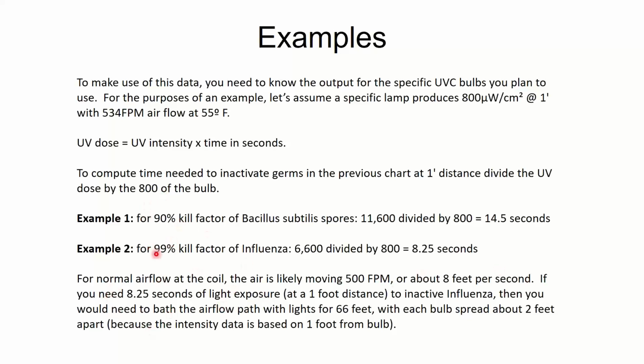I was already starting to jump onto the influenza one. Sorry, that was the bacteria one, 14 and a half seconds. Influenza, to kill 99% of the flu, I need 8.25 seconds. That's the one I was describing here. So to get that kind of exposure to kill influenza in the duct, I'm going to have lights every 2 feet. So I got that 1 foot distance on each side for 66 feet of length. If you don't want to put that many in, okay, then you're going to have to slow down the air a lot, down to like 50 feet per minute instead of 500, which you're not going to be able to do for HVAC purposes. So will the UV light kill influenza and bacteria? Sure, but it's not going to kill much of it because I don't have enough light bulb shine time.